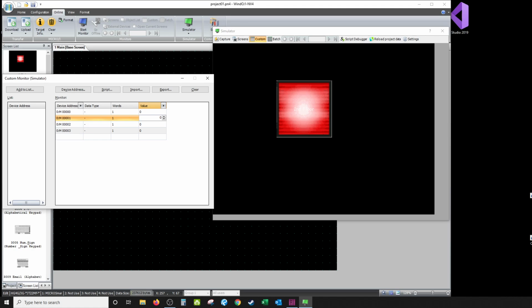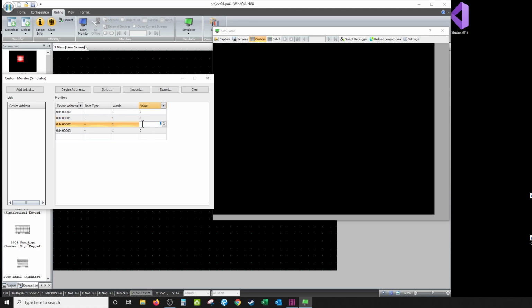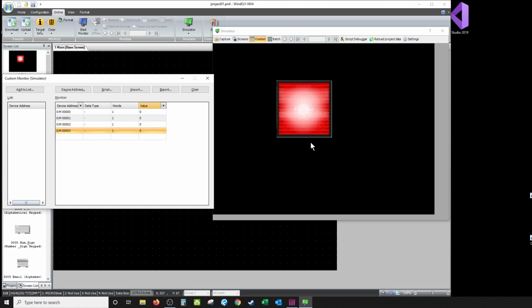Okay, I leave the second floor, and I'm getting to the third floor. I have my switch on my third floor, resets M1, and brings this one to set. So now my third floor light's on. Okay, I get to the fourth floor, my fourth floor switch resets that one to 0, it sets that one to 1. And that's something you just got to write in the logic of your program. I'm just kind of telling you that because that's an idea of how you could do it on rising edge and falling edge. Have it the falling edge of M2 or the rising edge of M3 reset M2 basically. But I hope that kind of shows you how to do this.